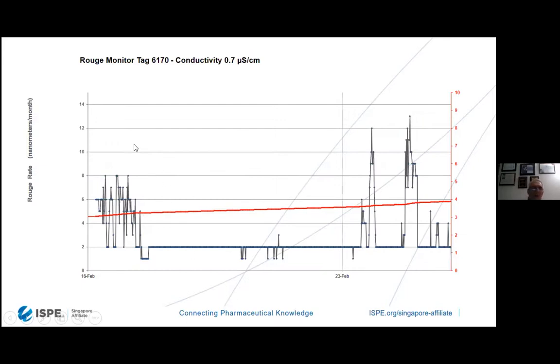So this is a hot water WFI system running at 80 degrees Celsius. The hot water heater comes on when it goes below 80 degrees C, and it takes it up to 85 degrees C. So when the heater comes on, the rouge rate goes up because of the higher temperature. When the heater goes off, the rouge rate goes down. And when the heater comes back up, it goes back up again. And when the heater goes off, it goes back down. If you were looking at the mean of this data, it would be very flat, which is shown by the data over here on the left.